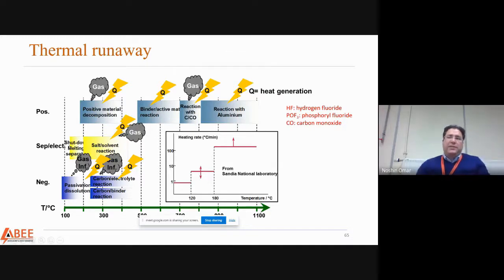When a battery starts initially failing, you don't see that. Internally it's creating gases, and slowly the battery temperature is increasing. When it reaches 100 degrees, dedicated components in your battery cell start failing. The first to fail are the protection layers, which we call passivation layers, and they start breaking.